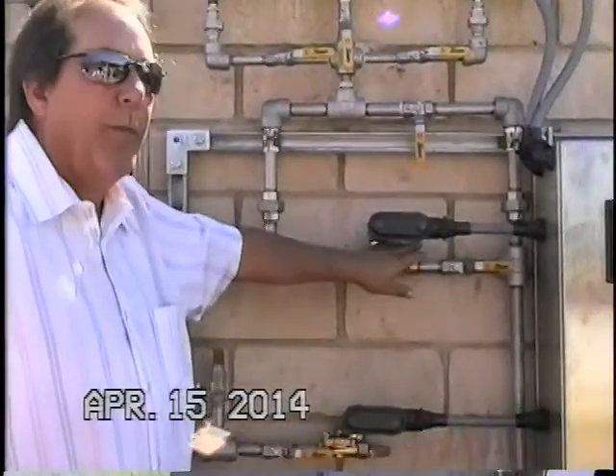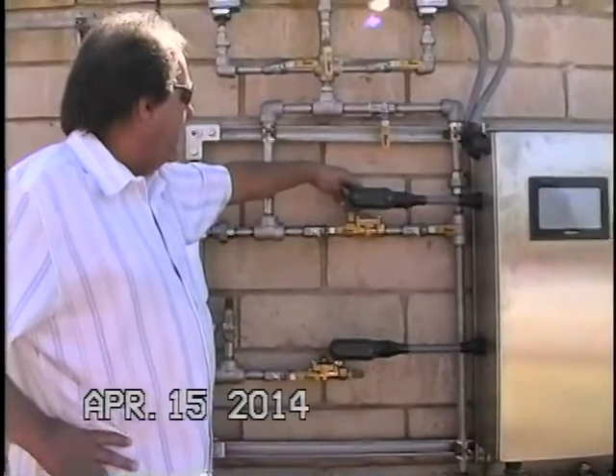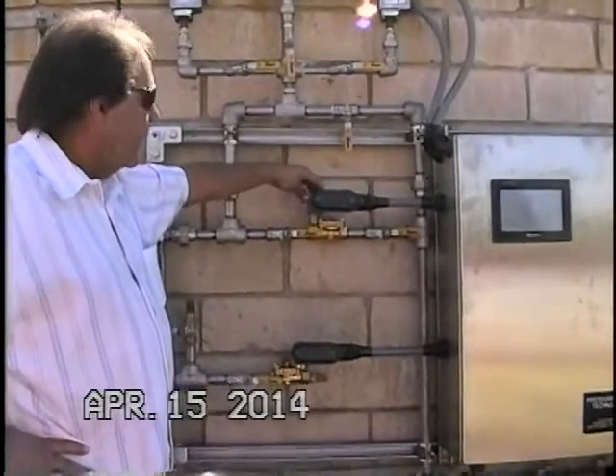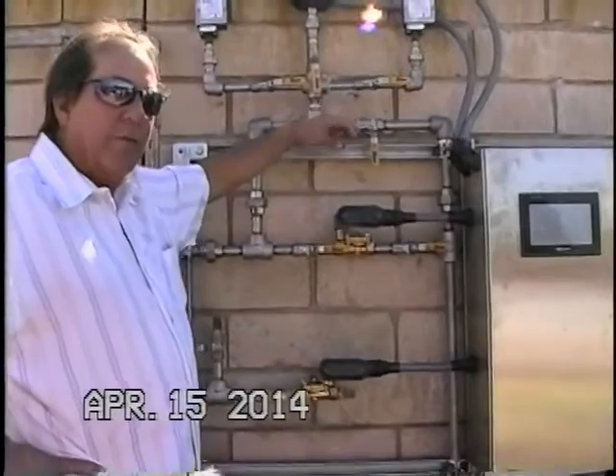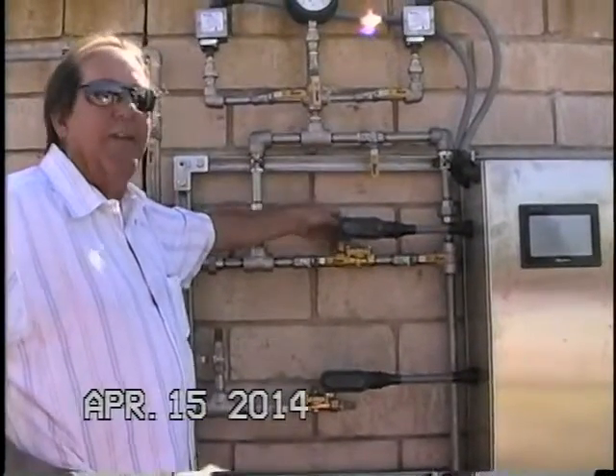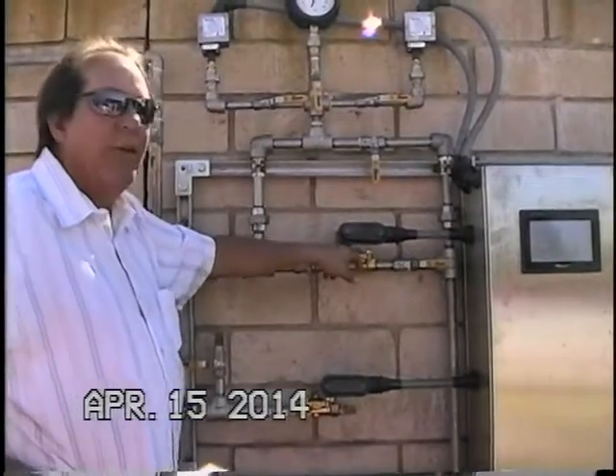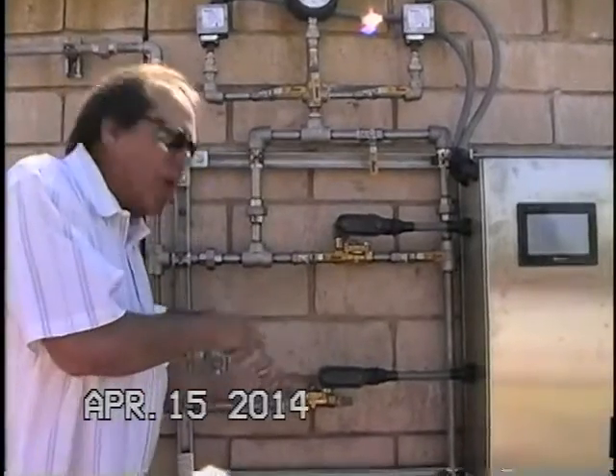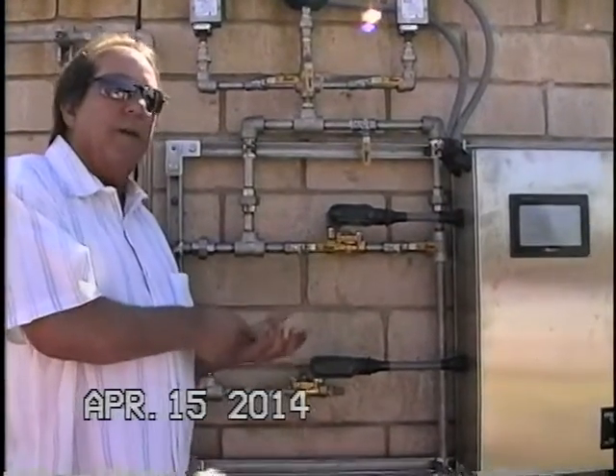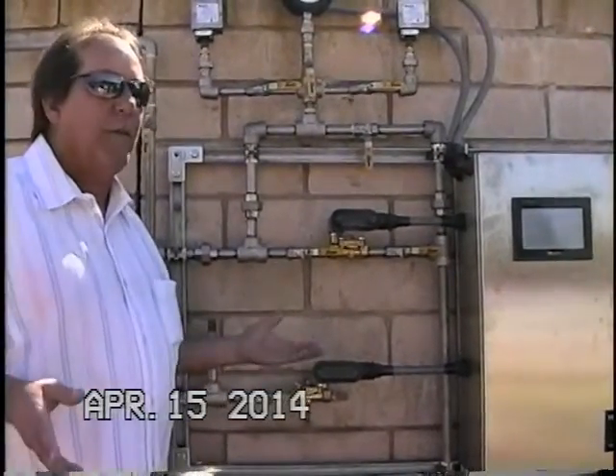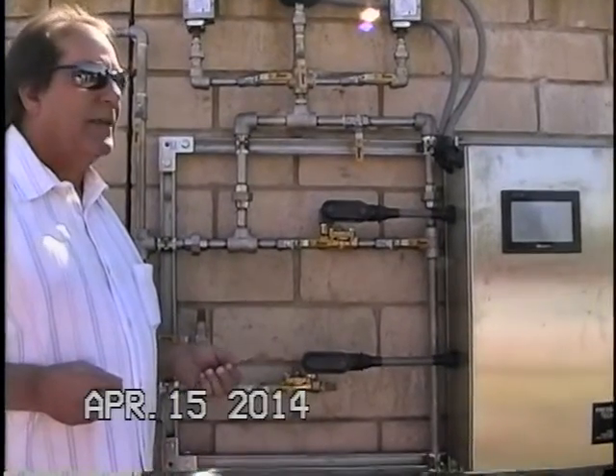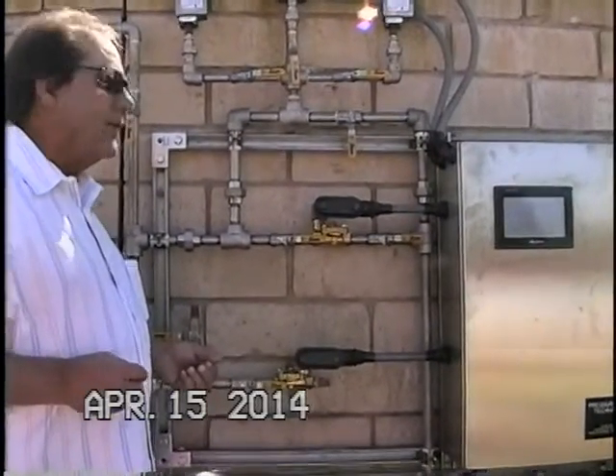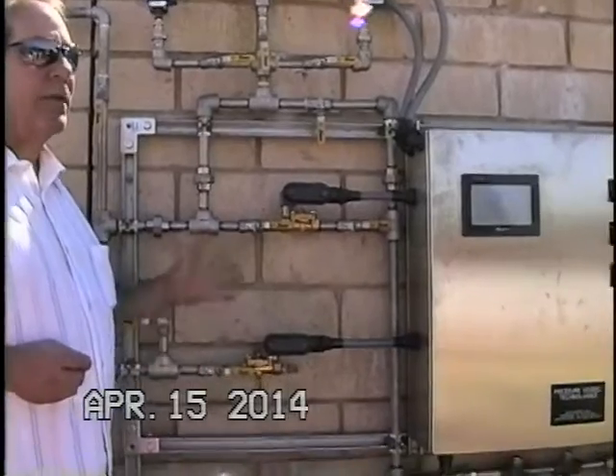You can take these 4 bolts off. The coil comes off. It's got a little clip. You can take the coil off. You can get to the body of the valve. You can go in there and look and see if you've got some kind of obstruction in there that's causing a problem. But typically, other than that, you really shouldn't have.